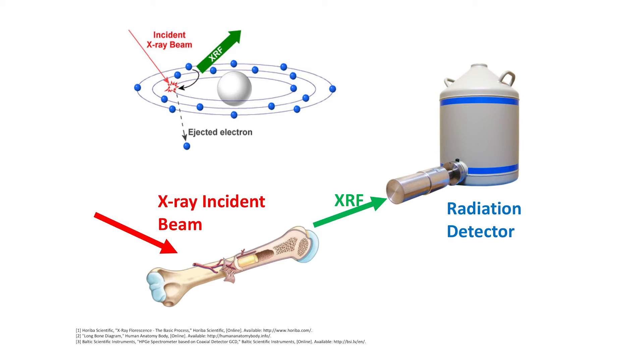This energy, called the XRF photon or fluorescence photon, will again travel in space until it reaches the third component of the system, which is the radiation detector.